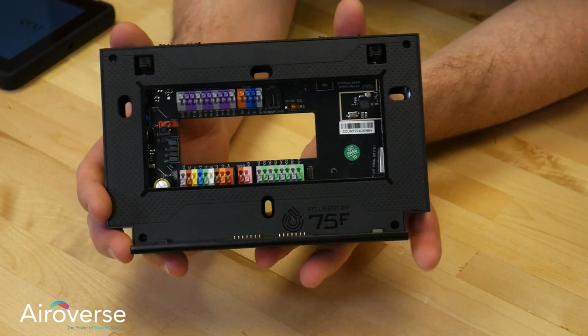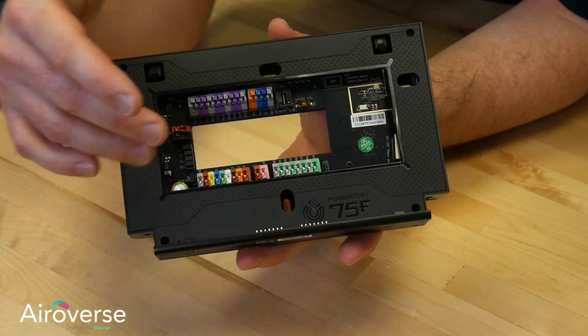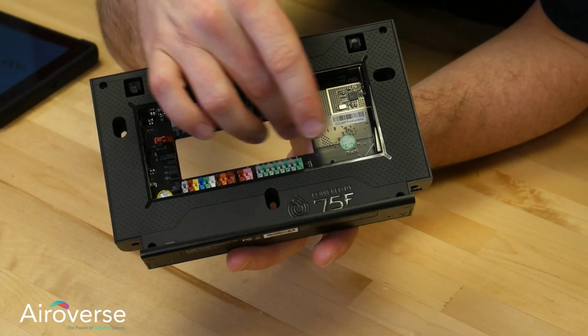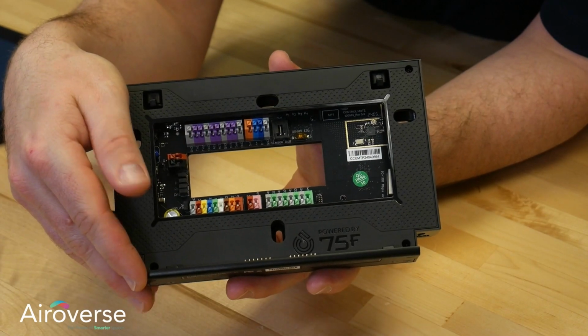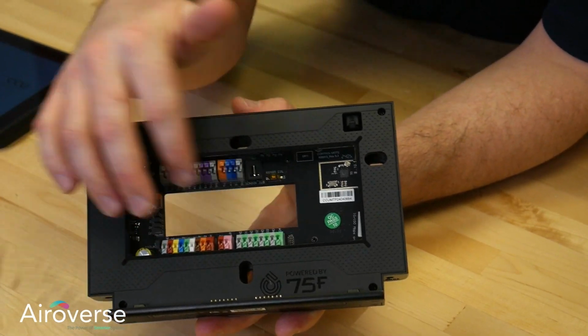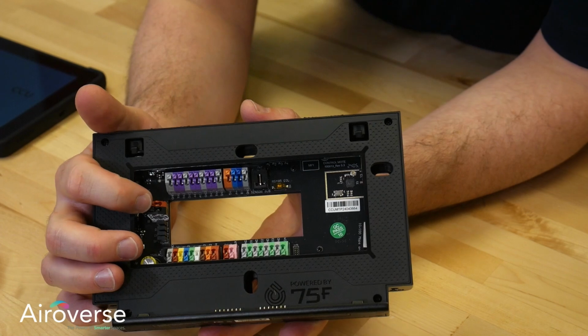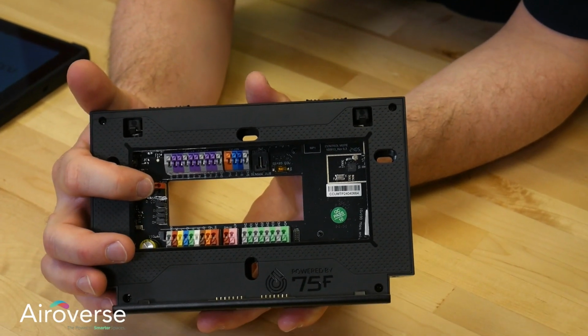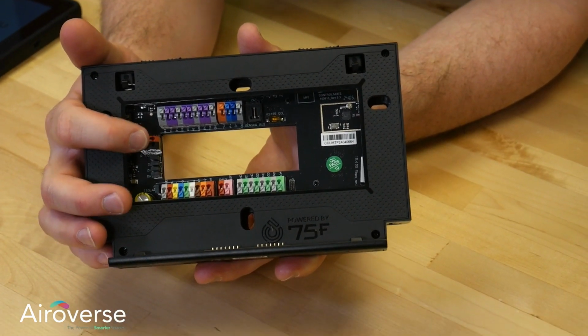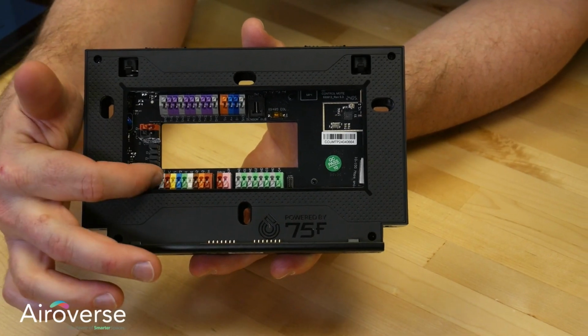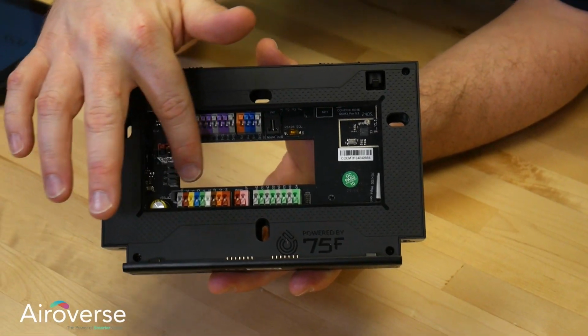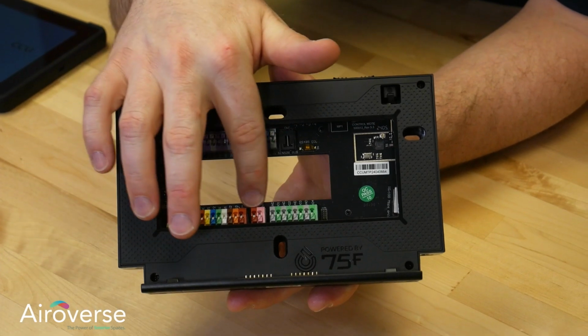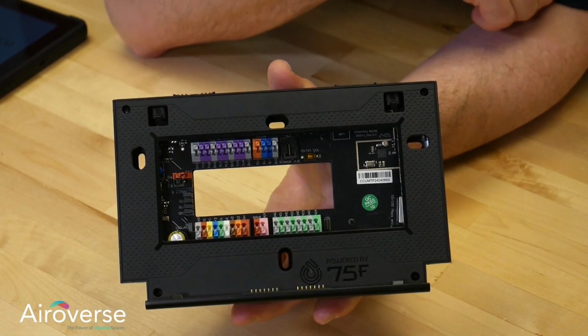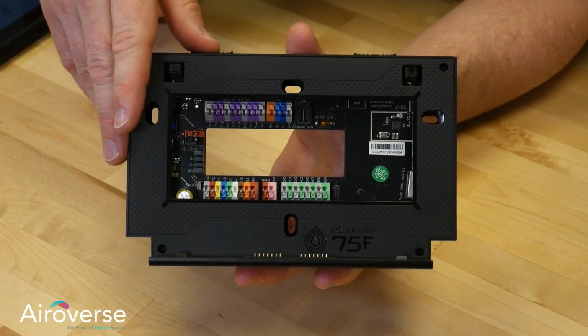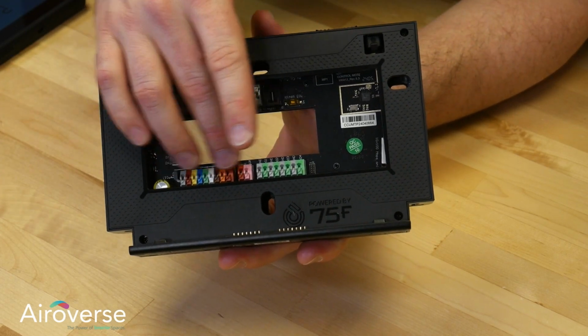So when you're actually wiring the device, after you get it mounted, you're going to bring your wires through the hole on the back, and then you've got some terminals on here. On the right side, I've got my dedicated power. This is 24 volts AC or DC. More often than not, it's going to be AC. On the bottom, I've got my electromechanical relays, just like a traditional thermostat. So this can act as the AHU controller in a multi-zone application.